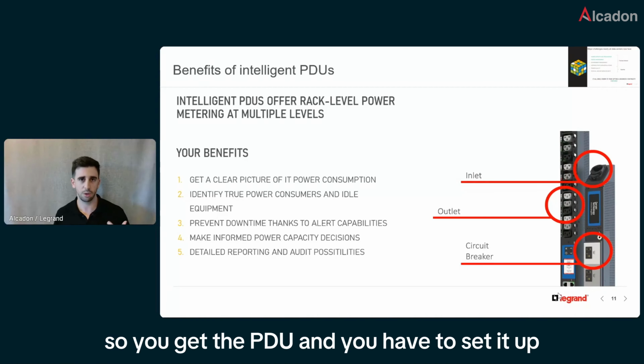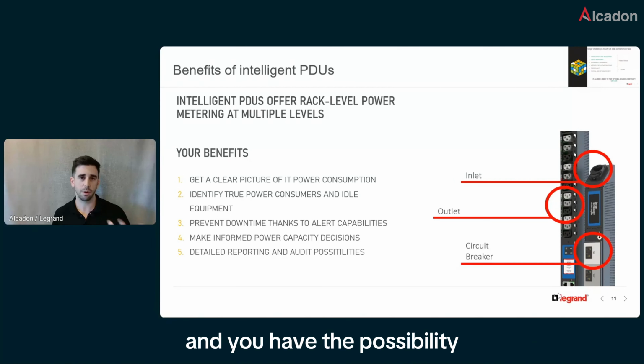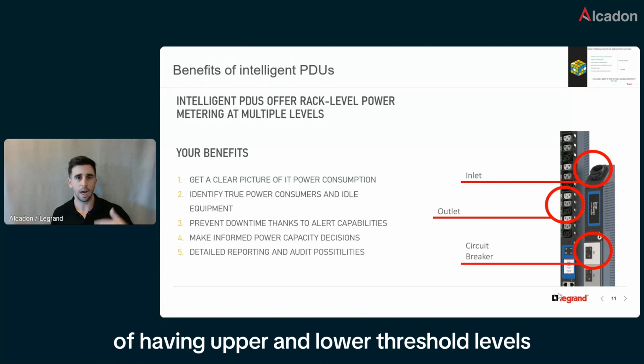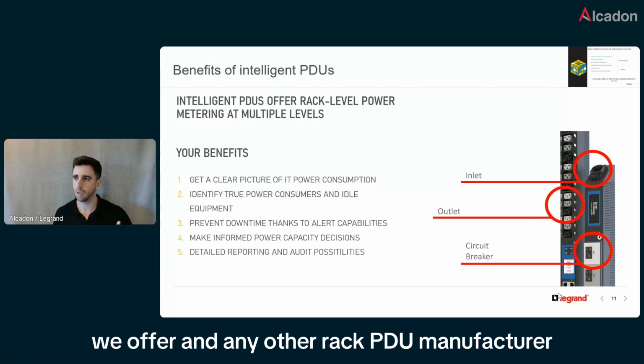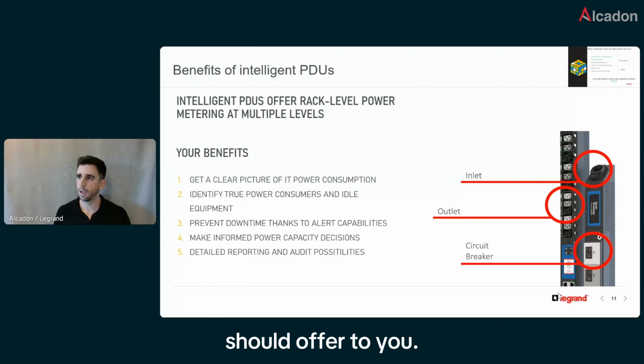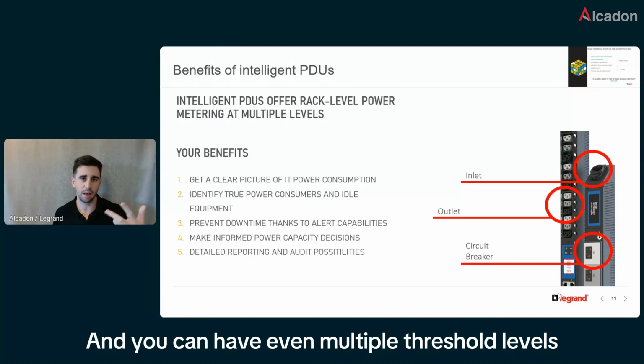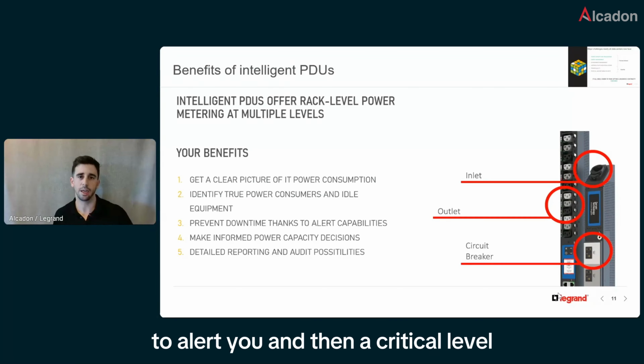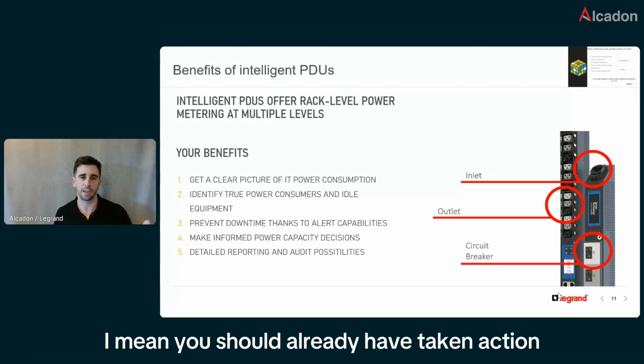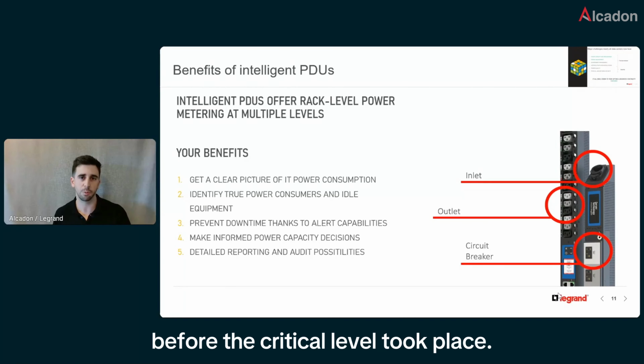So you get the PDU and set it up, and you have the possibility of upper and lower threshold levels for all the different metrics we offer, and any other rack PDU manufacturer should offer you. You can even have multiple threshold levels, like a first level to alert you, and then a critical level - you should already have taken action before the critical level is reached.